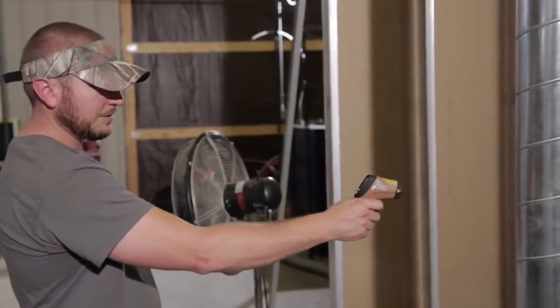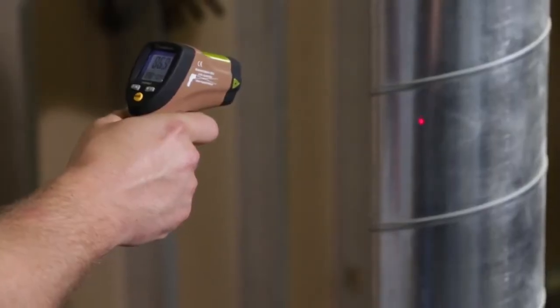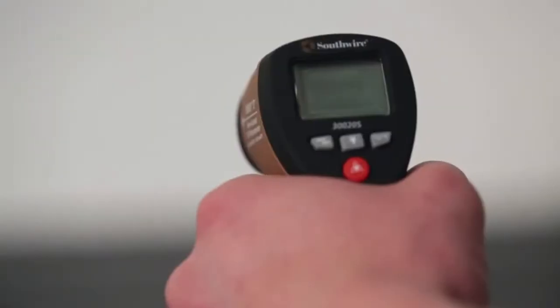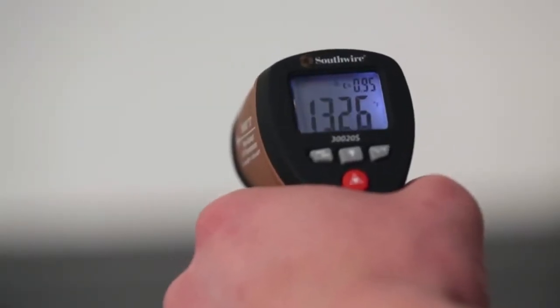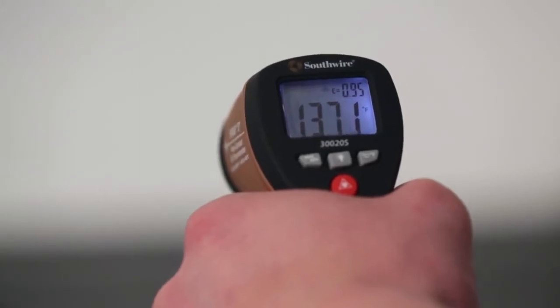Competitive models have lasers that are used for aiming only. They do not pinpoint the optimum distance, so it's much harder to get repeatable measurements. Adjustable emissivity compensates for errors when measuring objects that are reflective. This is primarily used when measuring temperature on unpainted metal like conduit. Response rate is important when scanning an area for temperature spikes. Simply put, the faster the response rate, the more accurately the IR thermometer will show hot or cold spots.